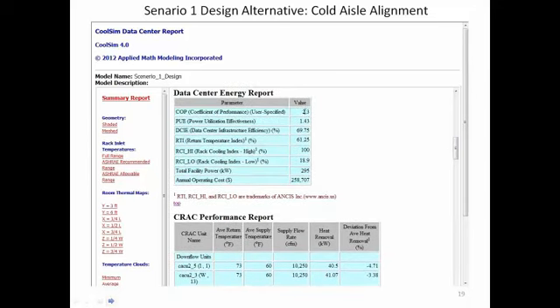That's an estimate. You can't always predict these things perfectly, but moving up a little bit is natural because the supply temps came up a little bit. And the RTI is 61%. It's about the same. This was 59 before, so that stayed just about the same. RCI, though, got better. Here before we were in the 90s, but not 100. So that got better. In other words, we're able now to distribute the air more effectively so that there's no hot spots in the room. But it's still very cold.